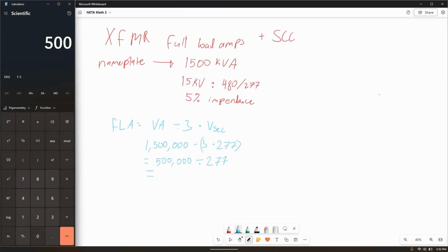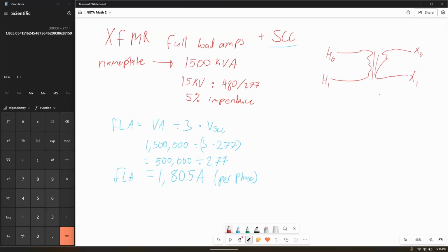And if I do that, that's 500,000 divided by 277. My full load amps, so the most that I could run this transformer, if we're running it at 100% load, the most I could run this transformer is 1,805 amps per phase. So that's how we solve for our full load amps. Under normal load, how much does the manufacturer say per this nameplate information? How much current can I draw all the time through a load, through a motor, through whatever it's powering? I can draw 1500 kVA or 1,805 amps per phase. That's how much I am permitted to pass through here.